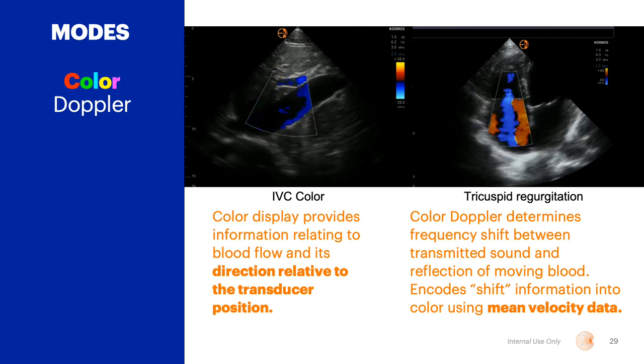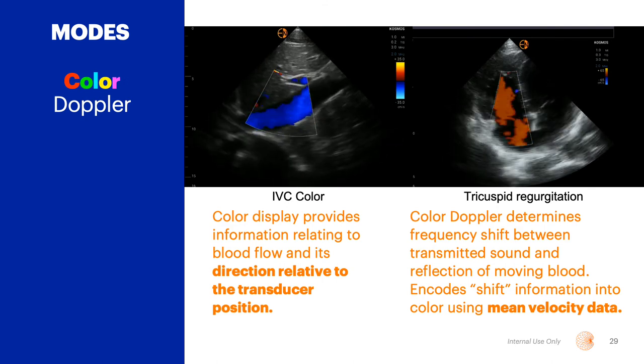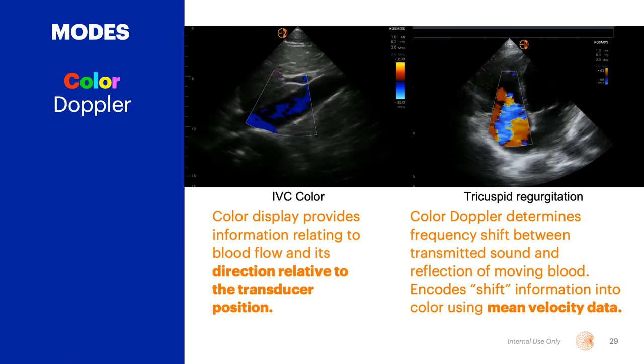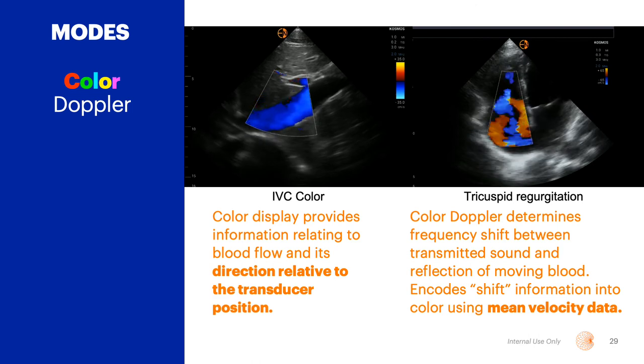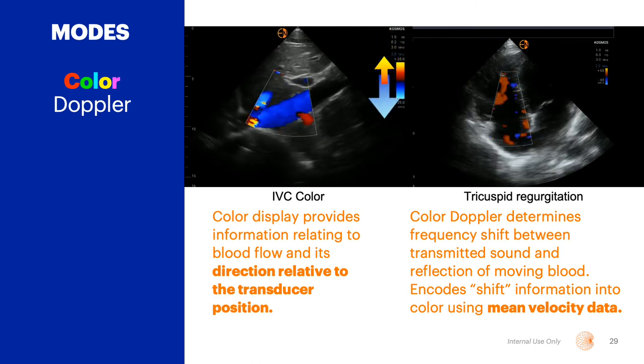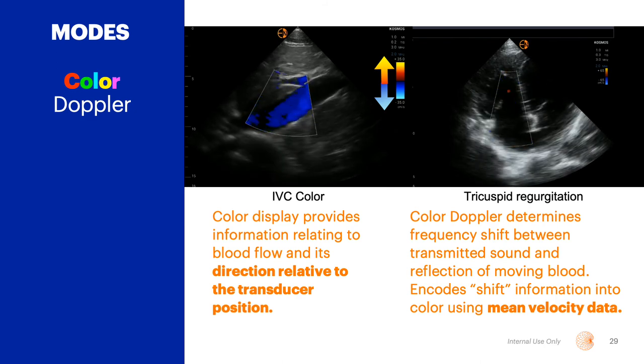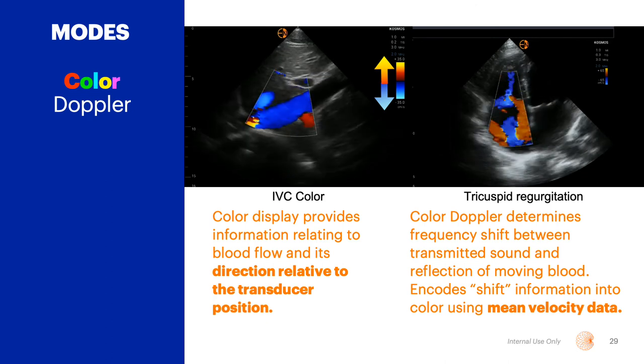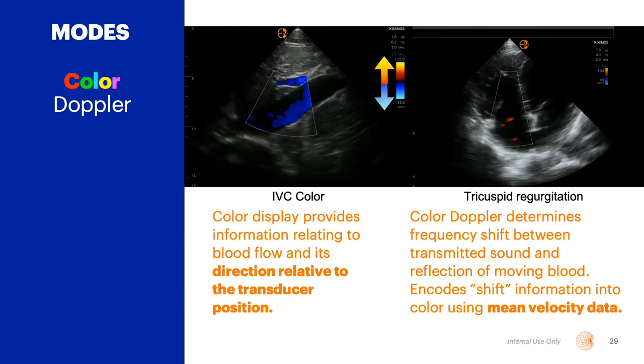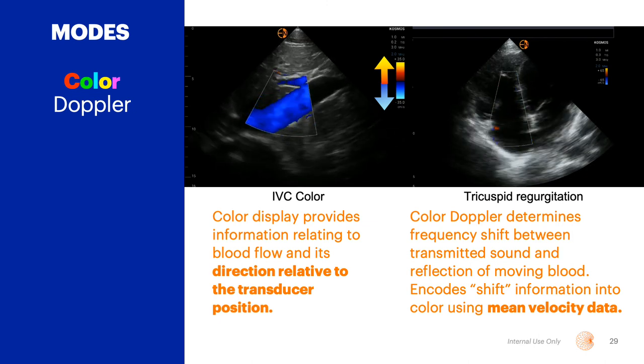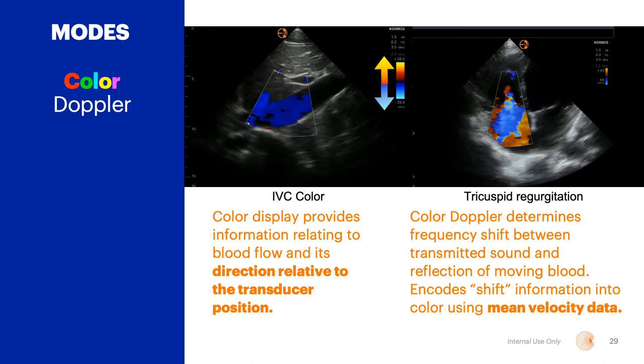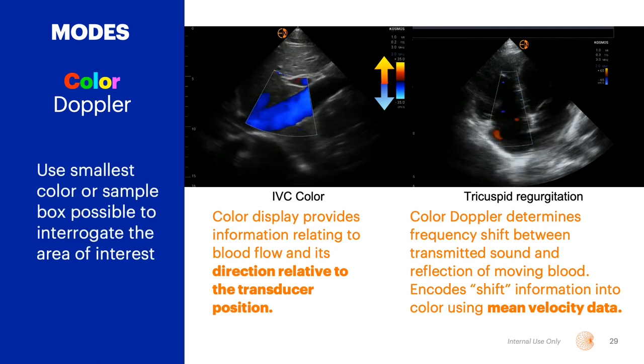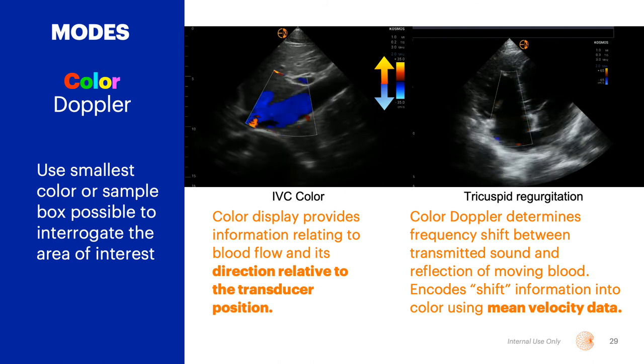Color and spectral Doppler are available on the Cosmos system. Doppler, including color, provides information relating to blood flow and its direction relative to the transducer position. Once color is selected, we examine the position of the color scale bars. In this example, flow towards the transducer appears in the red and yellow color scale, while flow away from the transducer appears in shades of blue. It is not a visual representation of arterial versus venous flow. Color Doppler determines frequency shift between transmitted sound and reflection of moving blood, and encodes the shift information into color using mean velocity data. Use the smallest color box size to interrogate the area of interest to maximize system performance and frame rate.